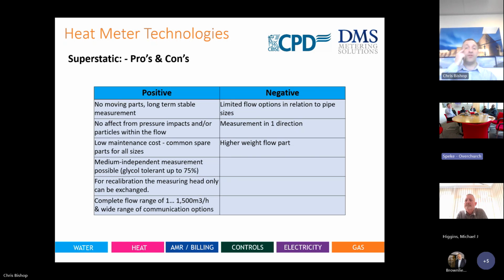Negatives: limited flow options. As a comparison to ultrasonics, you do have some limitation on ultrasonic, where a certain size has 2 or 3 flow options. The static option has 1 option per size. So that sometimes might mean the size is kept as it is, and we can't offer, let's say, a downsize option. But there are still reasons why that is relevant for the design of the meter.